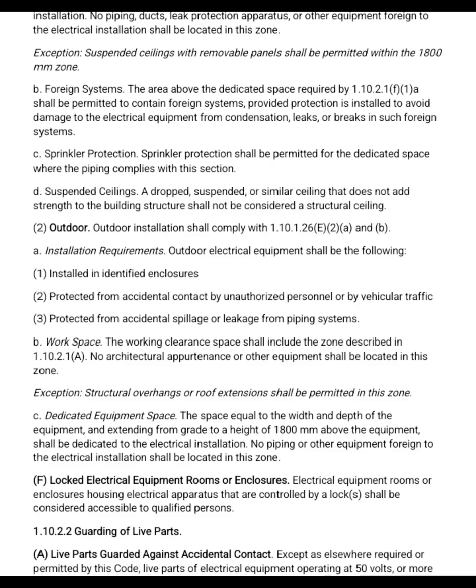A. Installation requirements. Outdoor electrical equipment shall be, 1. Installed in identified enclosures. 2. Protected from accidental contact by unauthorized personnel or by vehicular traffic. 3. Protected from accidental spillage or leakage from piping systems. B. Workspace. The working clearance space shall include the zone described in 1.10.2.1a. No architectural appurtenance or other equipment shall be located in this zone. Exception. Structural overhangs or roof extensions shall be permitted in this zone.